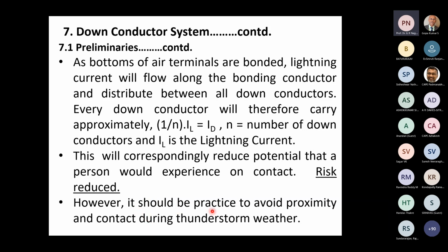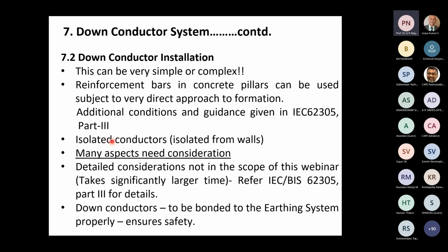So it should be the practice to avoid proximity also. Because as I told you, if you think of the worst case, 200 kiloamperes, these things can be very, very bad. So now, as I told you several times, the design and installation of down conductors can be very simple or very, very complex. It depends upon how the external surface of the building is. If it's simply a rectangular surface, 4 surfaces or 6 surfaces, it is easy to take the down conductor straight down. But usually buildings are not so simple in construction. There will be projections. There will be concrete blocks projecting, maybe for housing some things, or maybe for rain protection, what we call sejas in our country, concrete projections.